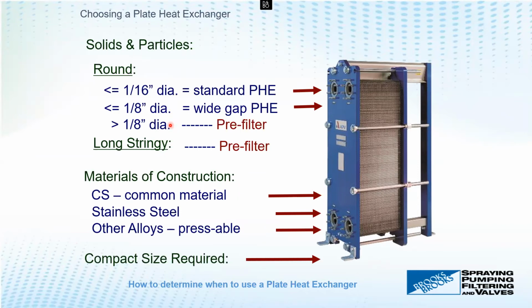Once we start getting above 1/8 of an inch, we have to start thinking about pre-filtering. We here at John Brooks are experts at filtering in all ways, shapes, and forms. Just because you have things that are larger or long and stringy shouldn't stop you from considering a plate and frame heat exchanger. We can definitely help with the filtering, pre-filtering, whether that's raw river water, well water, or pulp and paper with stringy pulp in it. We can get you there so your plate and frame can have a nice long run time.